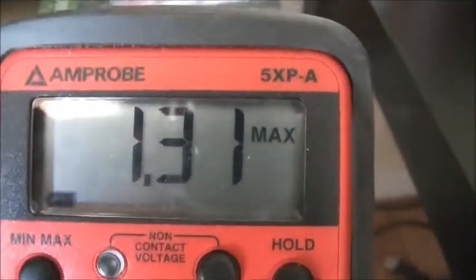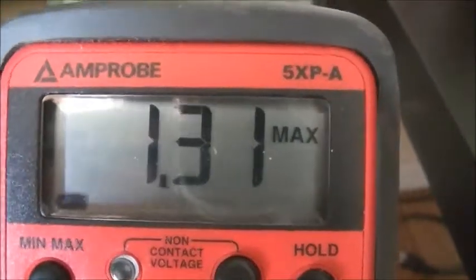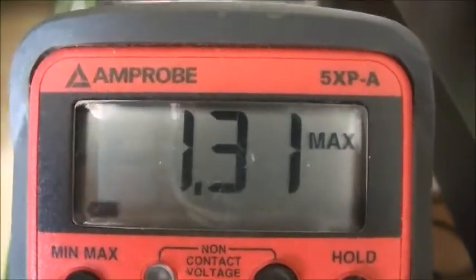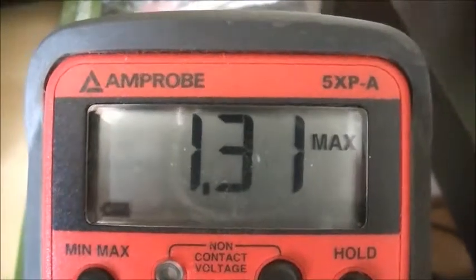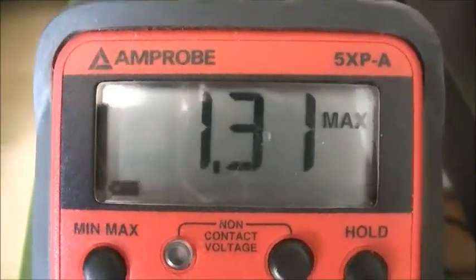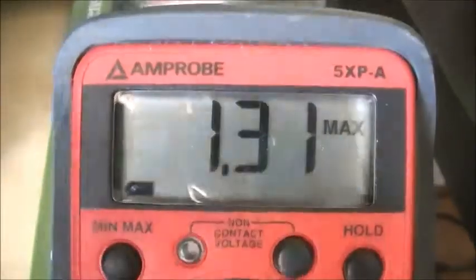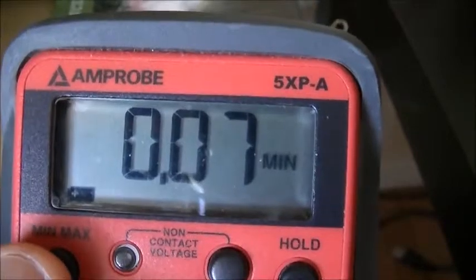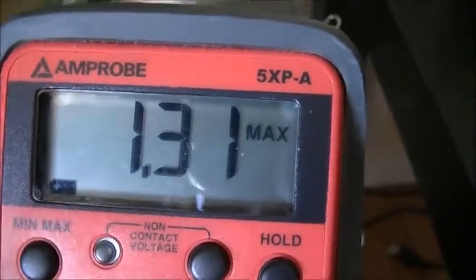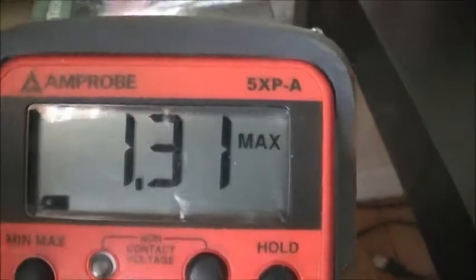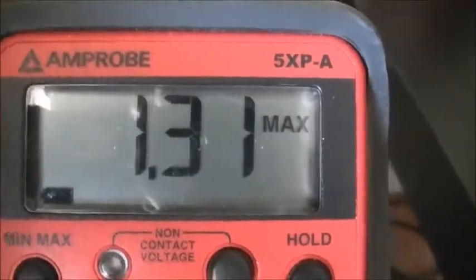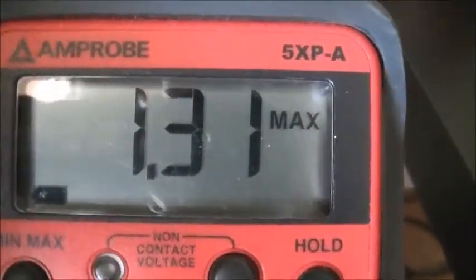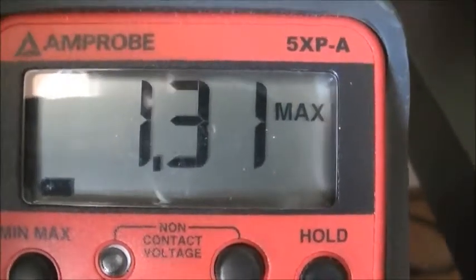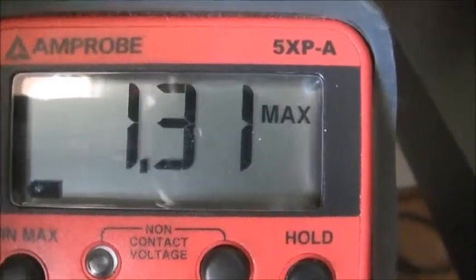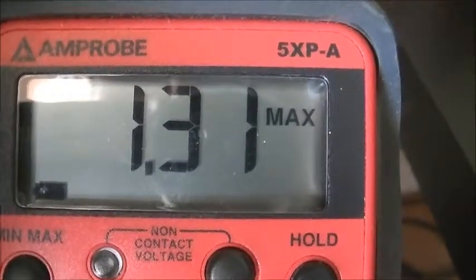This meter has been logging the value of the electrical grounding system over the last 24 hours. We have a maximum value of 1.31 volts AC on the electrical grounding system. Let's look at the minimum value: 0.07, so that's not a problem. But the 1.31 is a problem, because there is a limit of half a volt set for health reasons on the AC electrical system. As you can see, this far exceeds that limit.